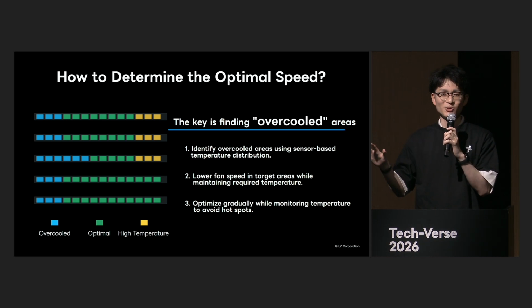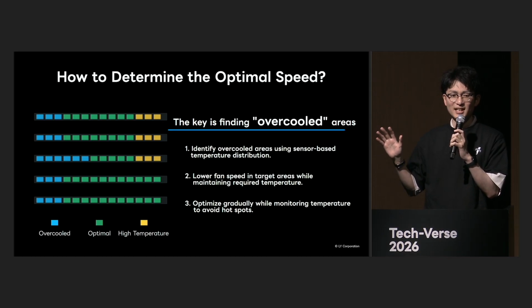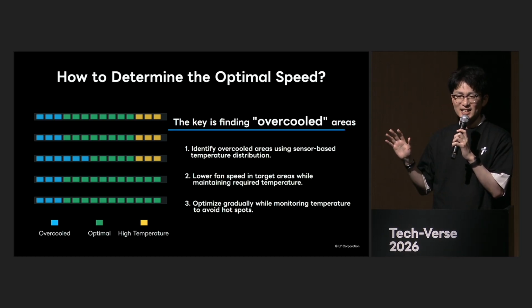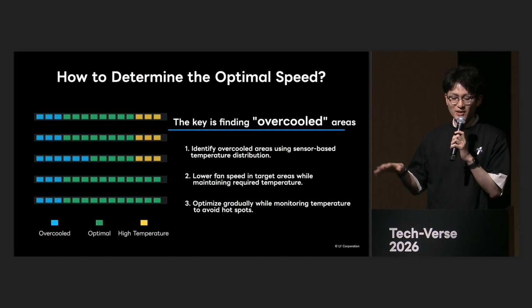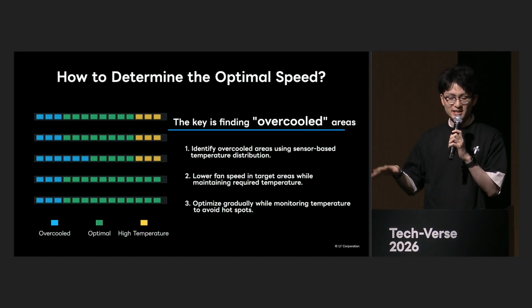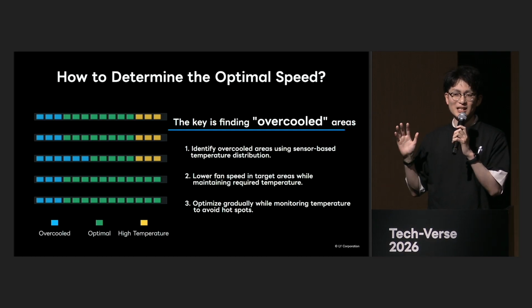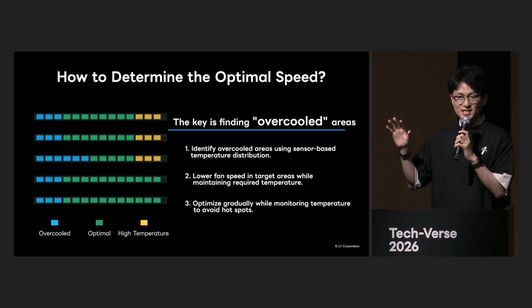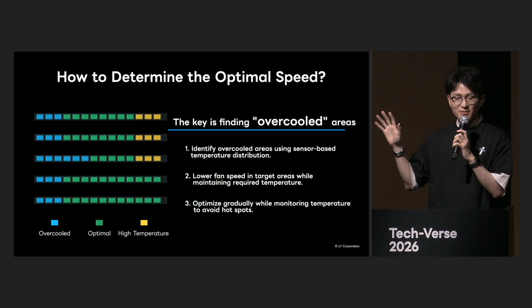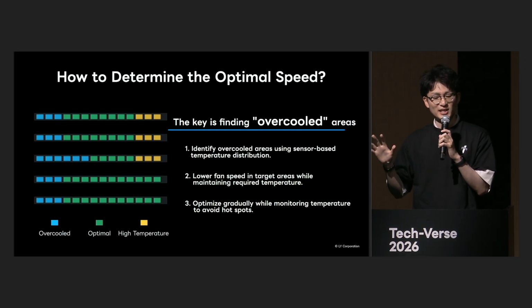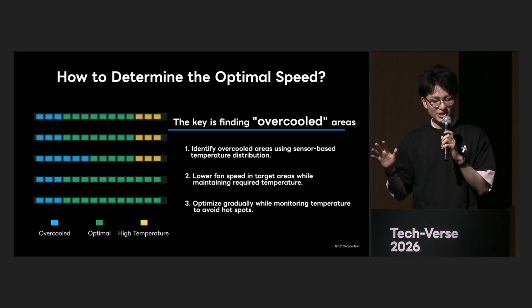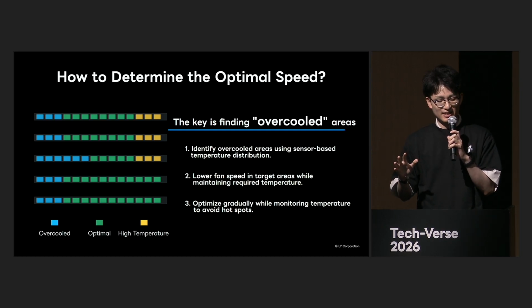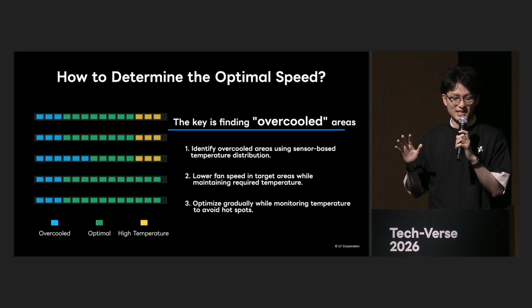Conventional air conditioning control either keeps the blowout temperature constant from the air conditioner, or controls the fan speed based on a table decided in advance. That approach was common. However, with this method, we are not able to properly anticipate the flow within the complex temperature management of the server room, even if a hotspot temporarily occurs.